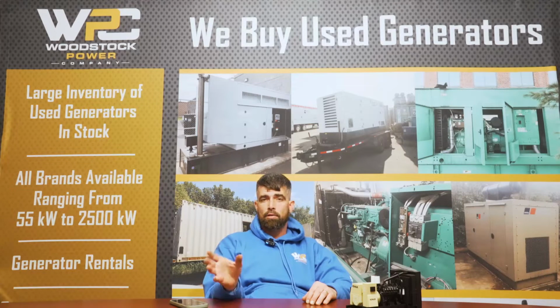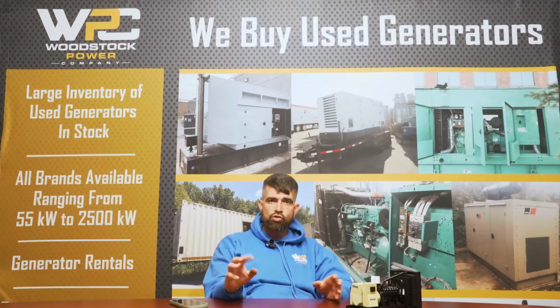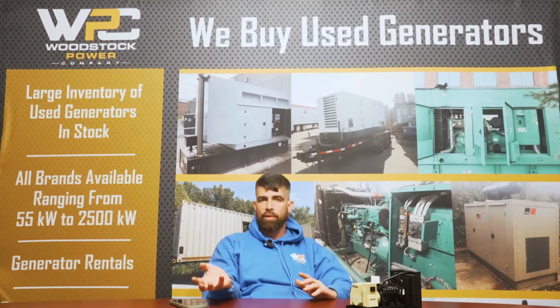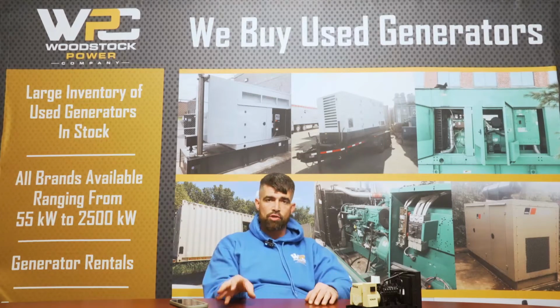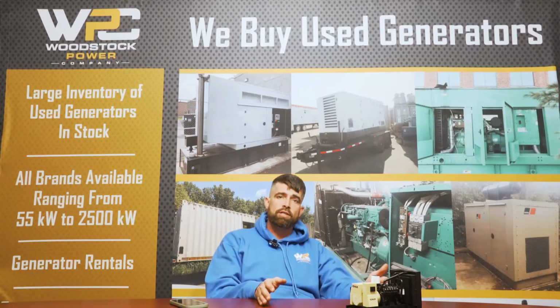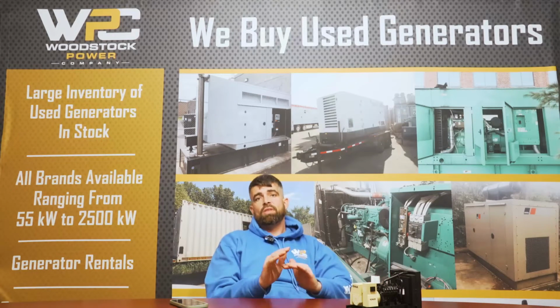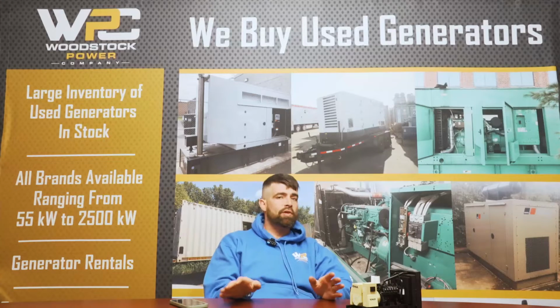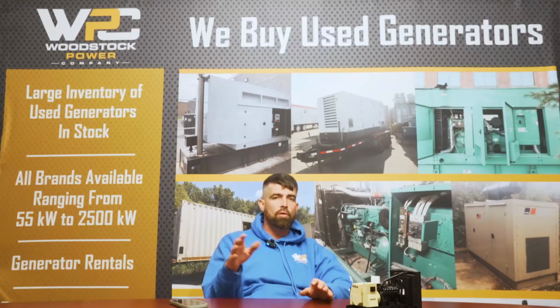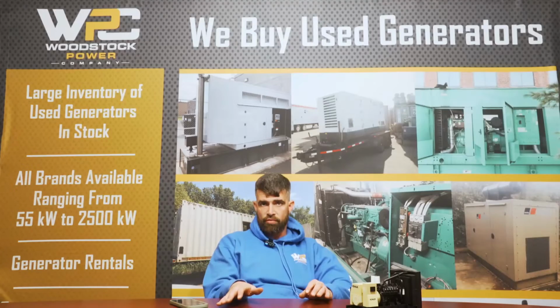We recommend on standby machines, about every 200 to 250 hours, again, depending on application, the size of the generator, the manufacturer, to do a full service on the machine. So make sure that it hasn't been about 250 hours since your last service. Make sure that the generator is ready to go. So anything that you can see that can eventually hurt it or affect it negatively, make sure you inspect first.